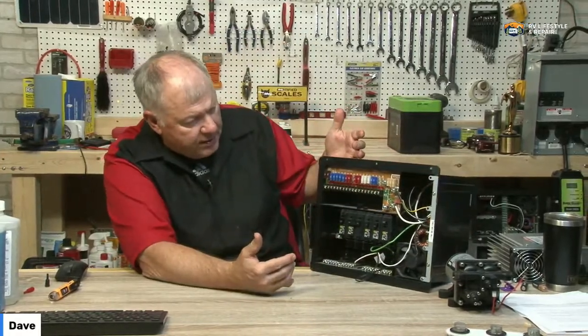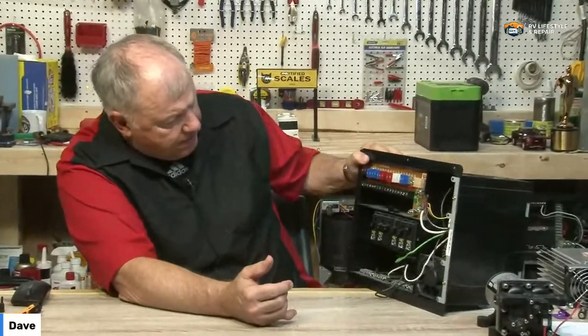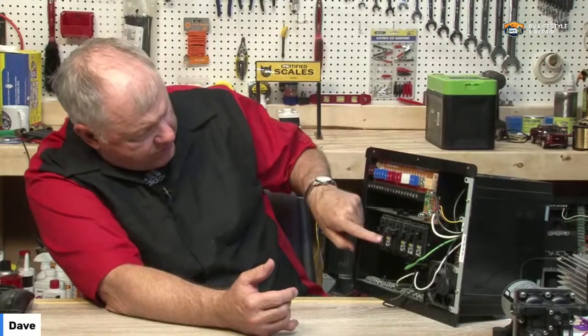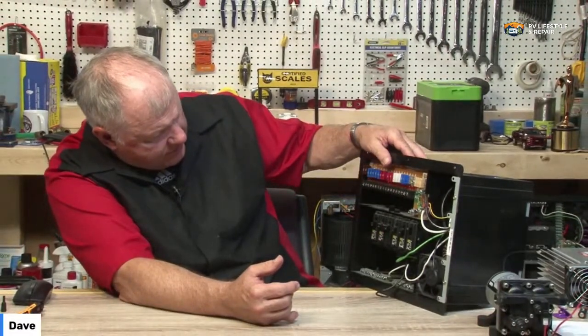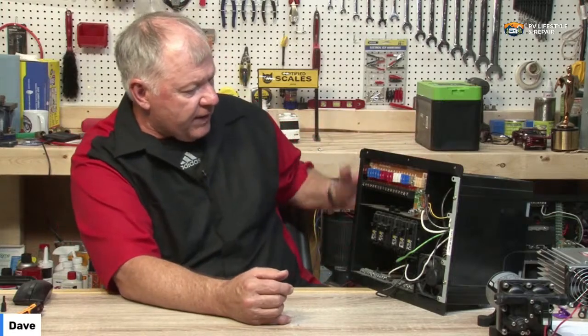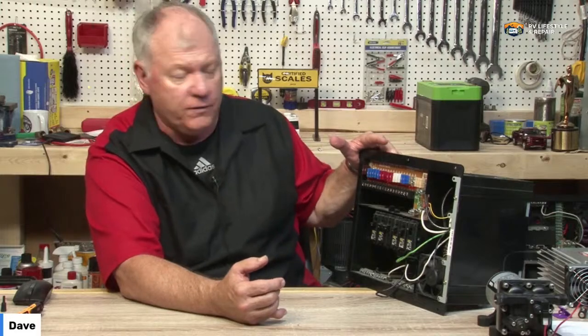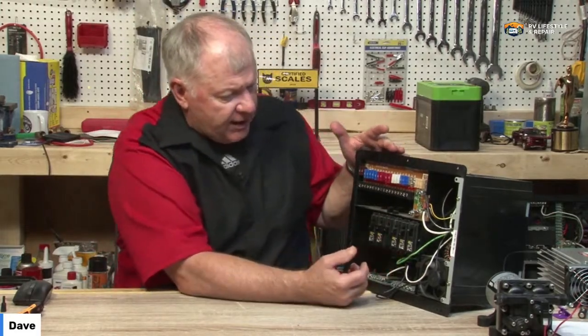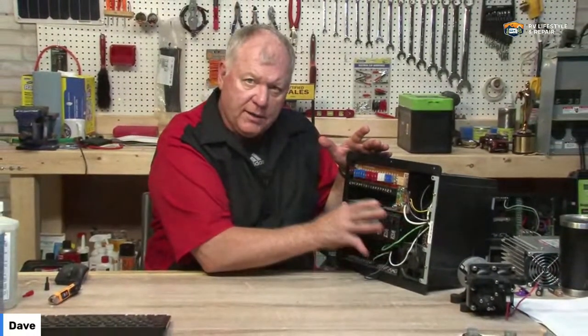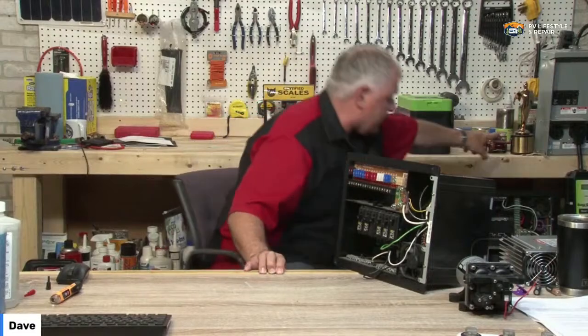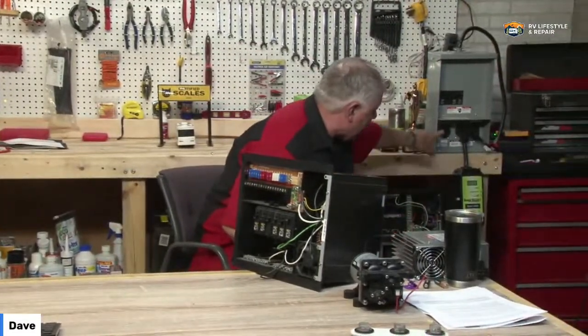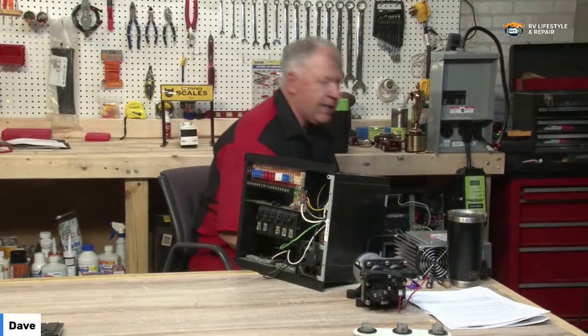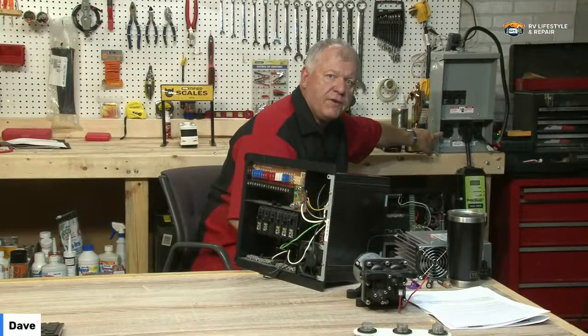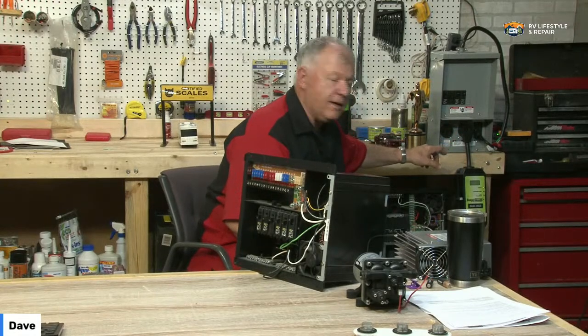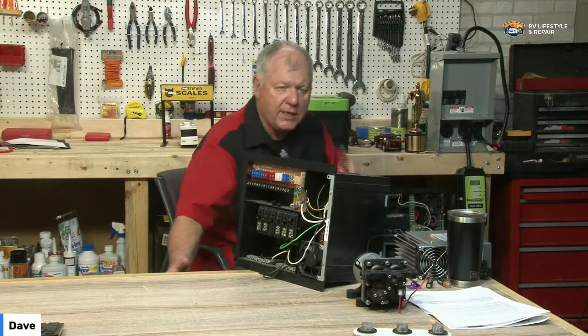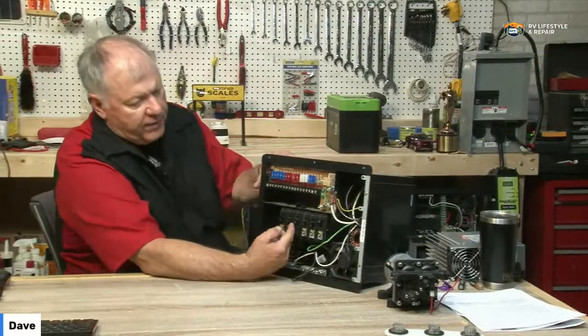This is a 30 amp distribution center. Instead, what you're going to have to do is change out the distribution center first, because in a 50 amp service you're basically going to have a split of this. In a 50 amp, you have L1 and L2 on each of these sides, so you have 120 volts at 50 amps here, and 120 volts at 50 amps there, rather than just the three-wire one we have here, which only has L1.